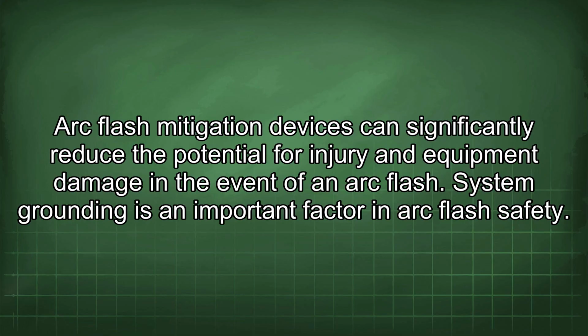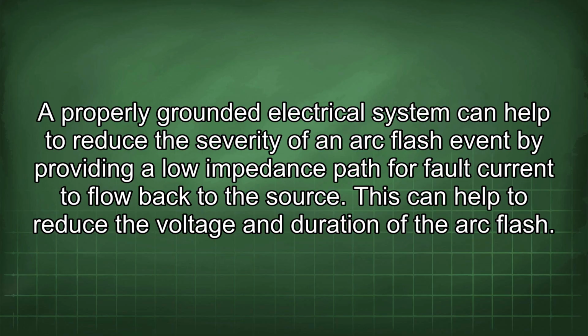System grounding is an important factor in arc flash safety. A properly grounded electrical system can help to reduce the severity of an arc flash event by providing a low impedance path for fault current to flow back to the source. This can help to reduce the voltage and duration of the arc flash.